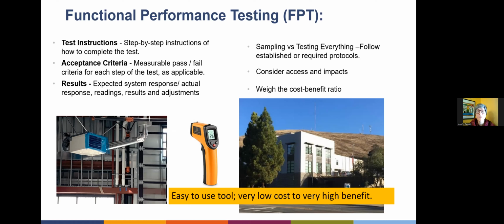And they can do all of the pieces of equipment, for example, need to go through functional testing, but your commissioning agent can do sampling, and it's usually a ratio of like 1 to 6. So they might get a stack of like 7 papers that have been filled out for the functional testing, and then the commissioning agent could randomly choose one and say, okay, walk me through this. Let's make sure this thing is really working.